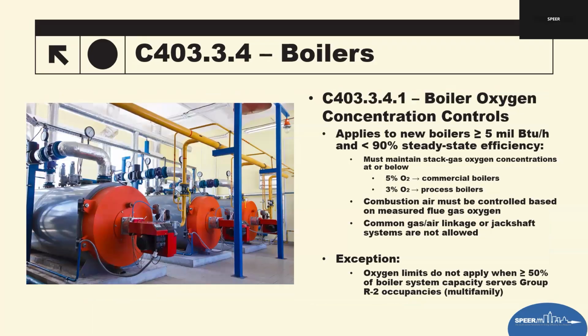Staying on boilers, we've now also got oxygen concentration controls, the O2 trim. This is a significant update. The newer installed boilers, 5 million BTUs or larger, with a steady state full load efficiency under 90%, must maintain specific stack gas oxygen concentration limits. So 5% O2 for standard commercial boilers, 3% O2 for process boilers.